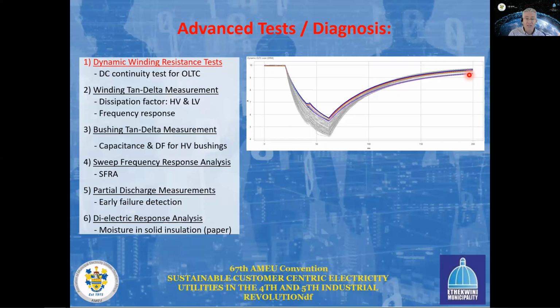This is a very good result that we see here, where the 96 curves are really all virtually on top of each other. The only reason why there is a bit of variation here is because at higher tap numbers, the current dips more because we've got less winding switched in our circuit. So this is very typical of what you see here.